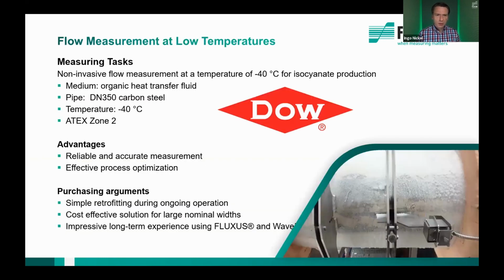And here you can see a cooling application at Dow. You see the pipe completely covered with ice due to the low temperature. This is a typical heat transfer application, which you find in the production of MDI, an isocyanate. During the purification of this MDI, heat must be dissipated from the process. For this, an organic coolant, which is cooled down to -40°C, is used as a heat transfer medium. And together with our wave injector, we can also provide a solution for this very challenging low temperature.